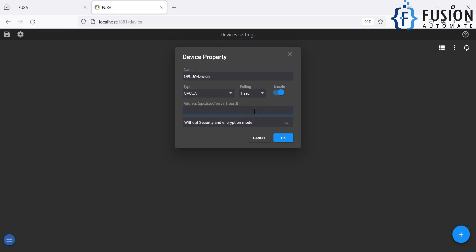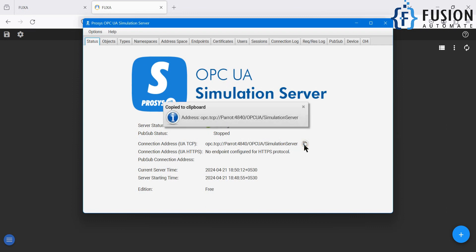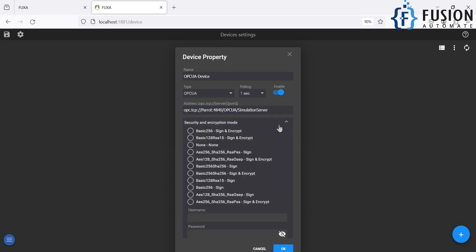If your Siemens PLC is in the field and is running the OPC-UA server, you can provide the endpoint URL of that Siemens PLC and have the data from it here in FUXA SCADA. If you have any other OPC-UA server running in your network or plant, you can provide its endpoint URL to read data from it. Here we have the OPC-UA Simulation Server, so we are going to copy and paste this endpoint URL. Then we have to select the security policy and the message mode, and if OPC-UA connectivity requires a username and password, you can specify them here.